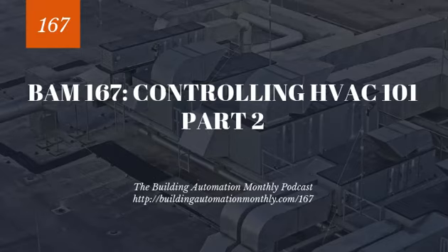I'm not saying proportionally offset dampers don't fail. I'm just saying that of all the times I've seen units damaged, most of the time it's improperly done on 100% outdoor air units or rooftop units, and someone's closed the dampers because maybe they reversed the state. I see this quite a bit on LON potentially, where they get the states wrong, and I see this sometimes on BACnet systems, depending on the manufacturer and how they reflect damper state. That's why it's so important to do point-to-point checkout.